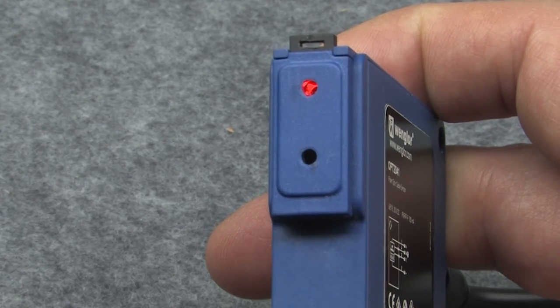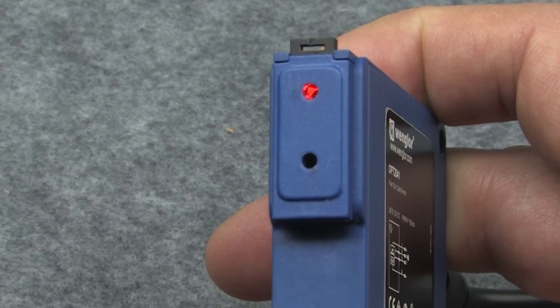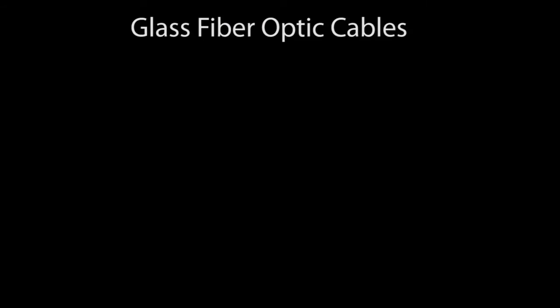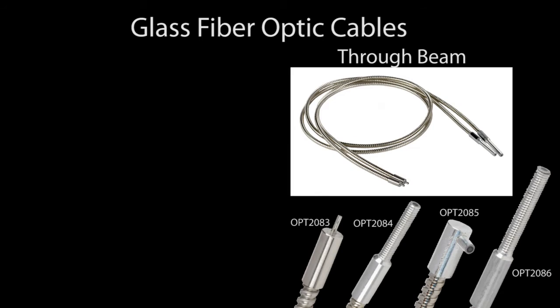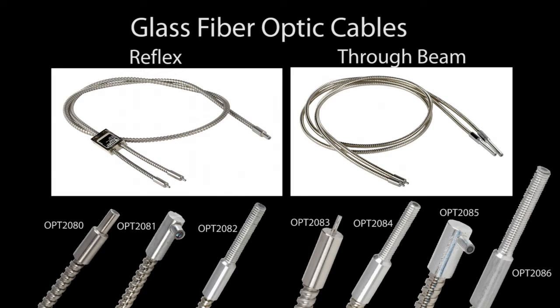With parallel fibers, it doesn't matter which hole you plug them into. There is also a variety of glass fiber optic cables in both through beam and reflex styles. These are ideal for harsh environments because of the steel jacket and because glass fibers are not as susceptible to corrosive environments as the plastic fibers are. Glass fibers can also handle higher temperature environments, although the plastic ones are a little better at the low end.